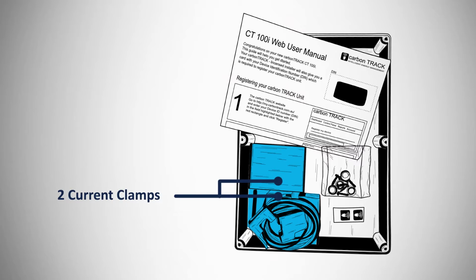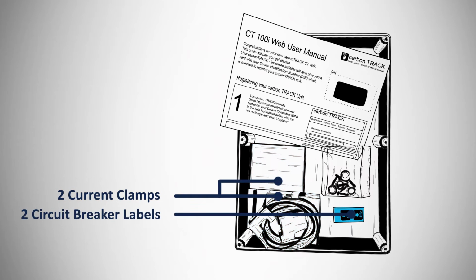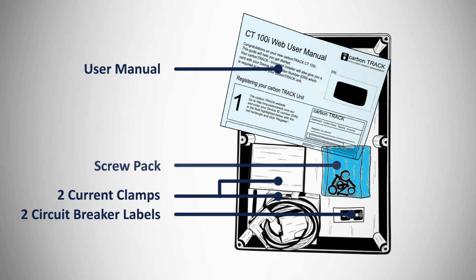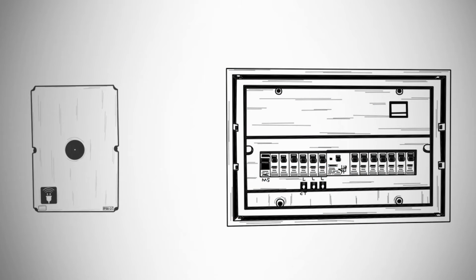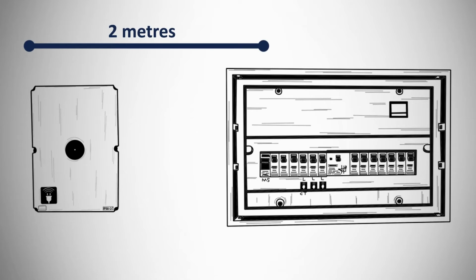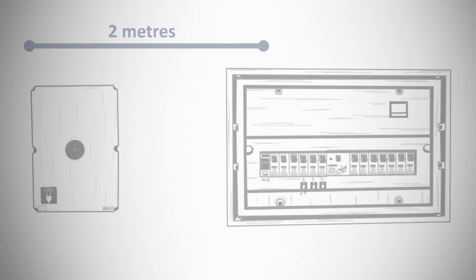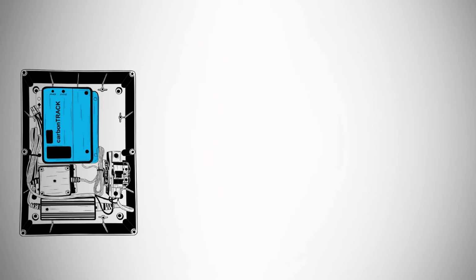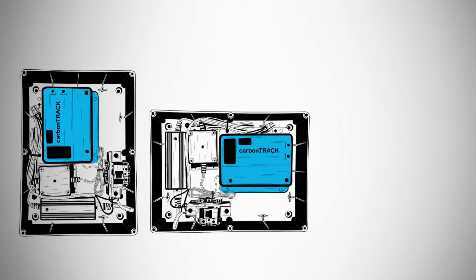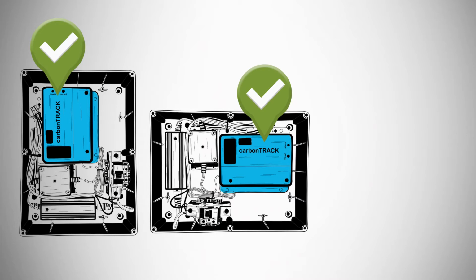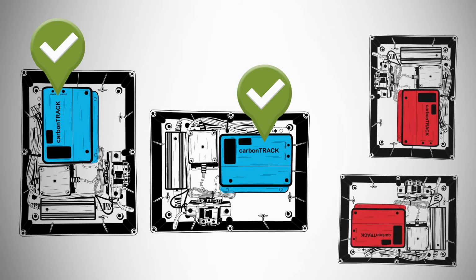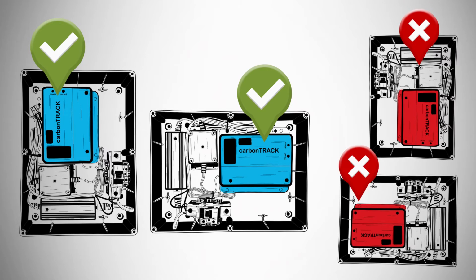Inside your CT100i kit, you'll also find some loose items: 2 current clamps, 2 circuit breaker labels, 1 user manual, 1 screw pack. The first step in the installation is to find a suitable mounting location within 2 meters of the electrical distribution board. The unit must be installed upright or on its side with the CT unit in the top right corner position. Do not install any other way.